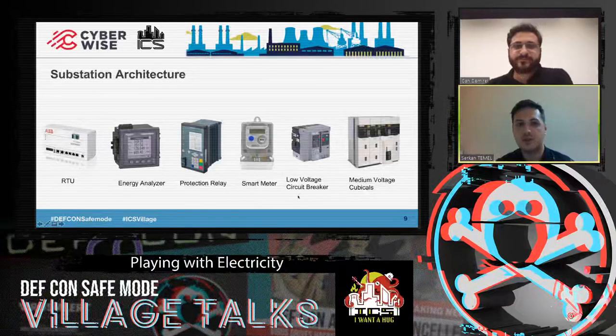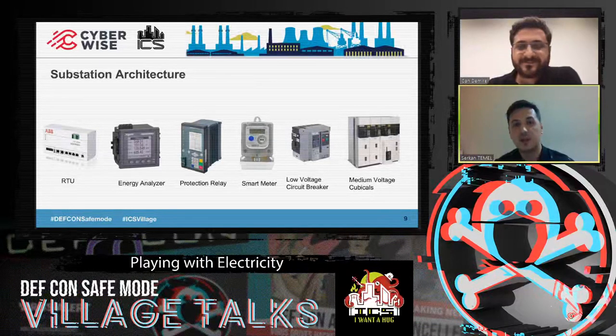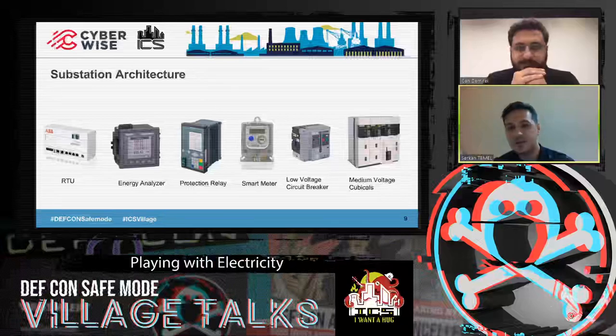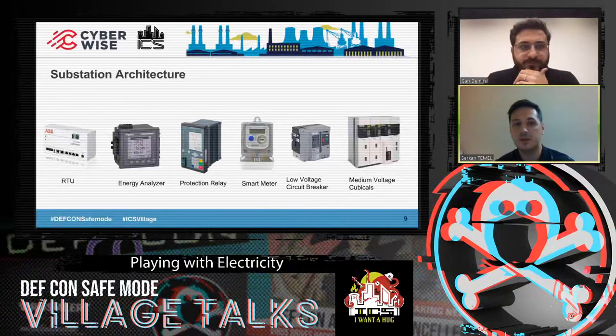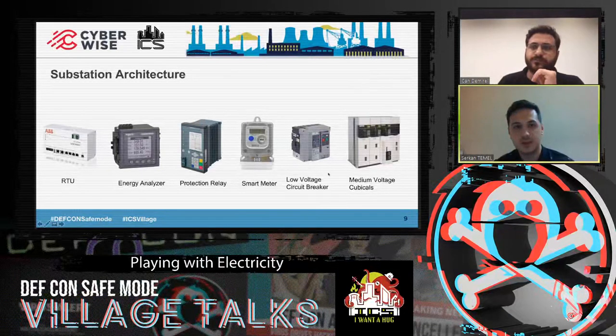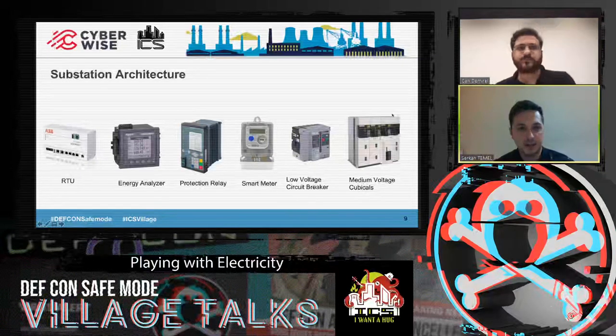Smart meter, as you know, is for billing purposes, and maybe on the low voltage side, for the customer side, to shut down electricity or re-energize electricity. These last two devices are physical devices. The first one is the low voltage circuit breaker. It controls the electricity line. And the last one is the medium voltage cubicles, meaning there are also circuit breakers inside these cubicles. They control the electricity line networks.